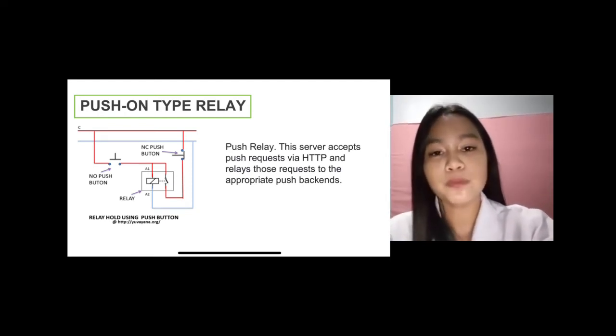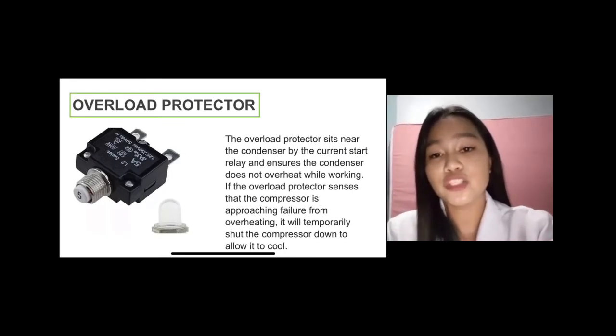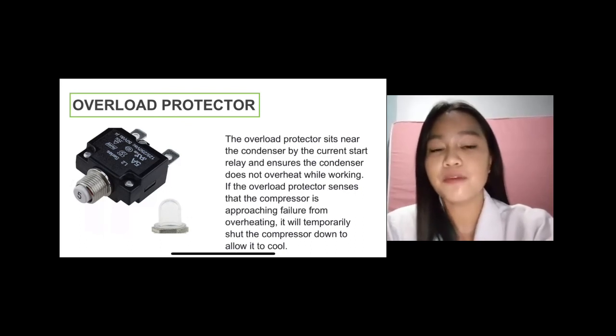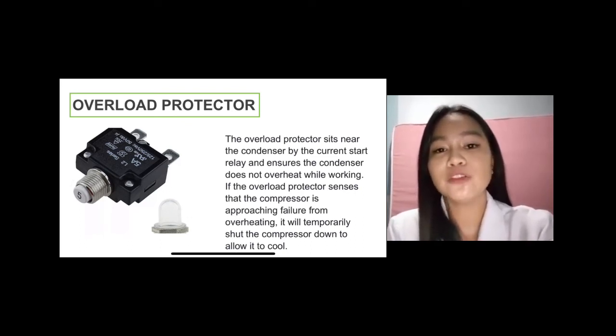Next is the overload protector. The overload protector sits near the condenser by the current start relay and ensures the condenser does not overheat while working. If the overload protector senses that the compressor is approaching failure from overheating, it will temporarily shut the compressor down to allow it to cool.